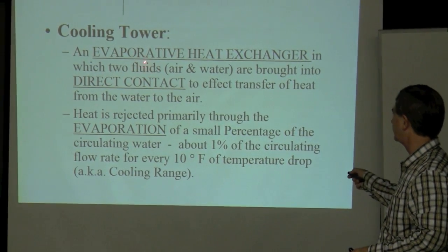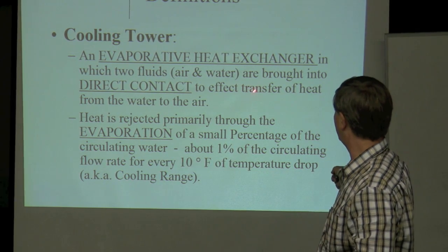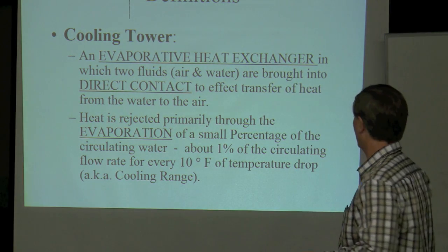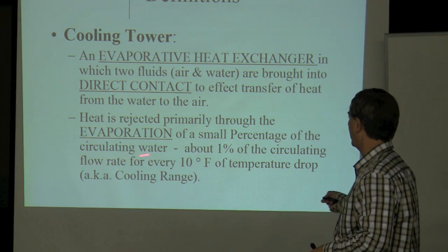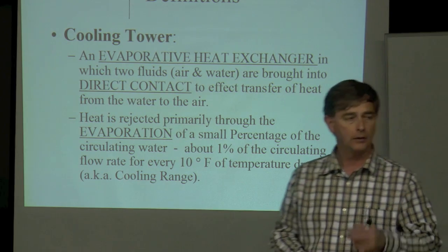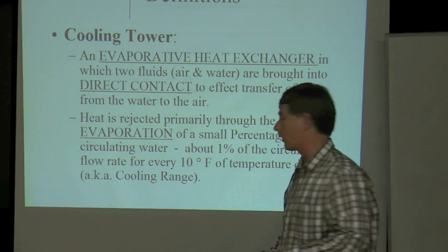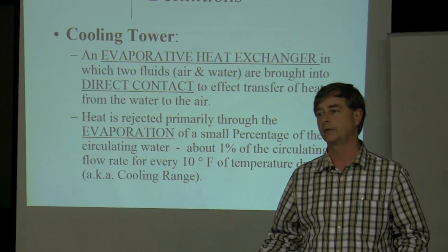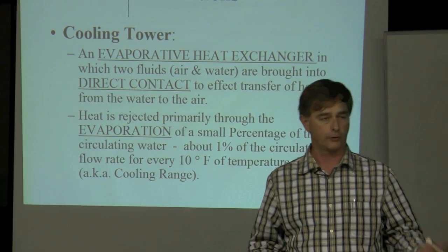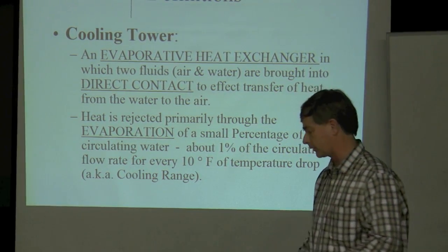Definitions: you're mixing air and water, bringing them into direct contact to transfer the heat from the water to the air, and it does that through evaporation. You will have some water loss — about 1% water loss through evaporation for every 10 degrees of temperature drop. Typically in our industry, cooling towers have a 10-degree delta T, so rule of thumb, you're going to lose about 1% through evaporation while circulating the water.